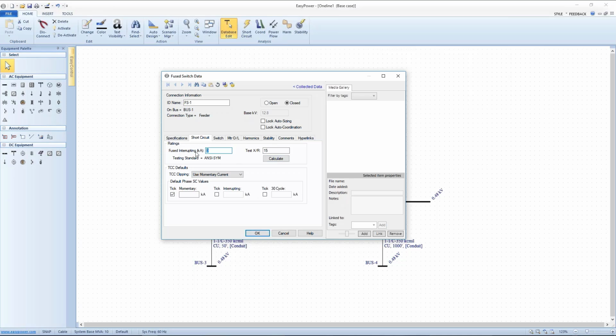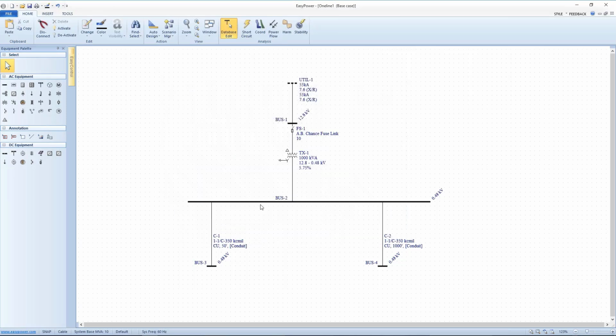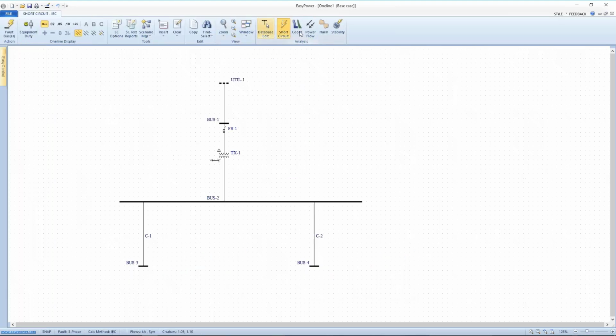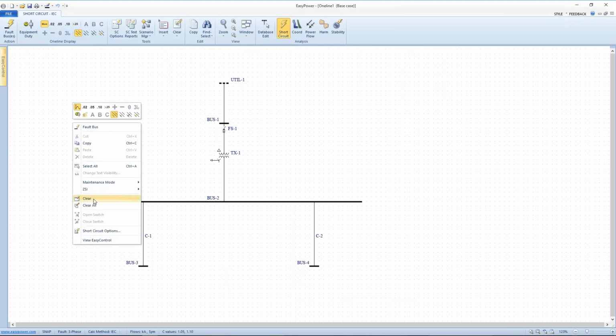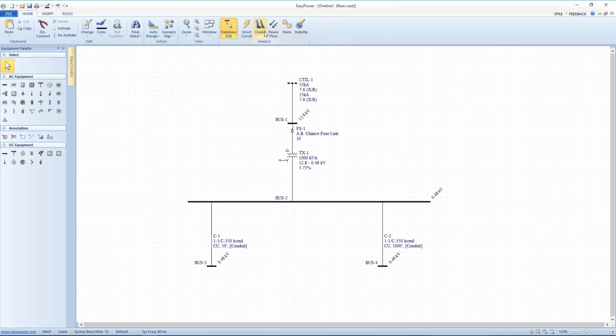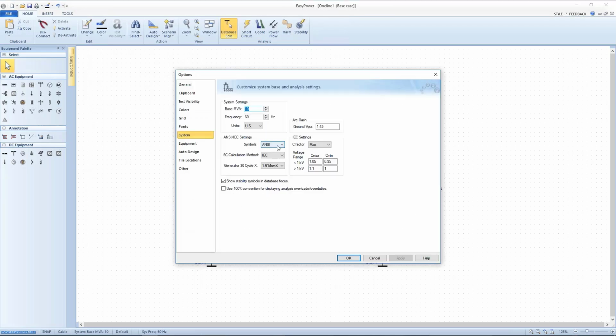Now, the interrupting rating in this case is actually that of the switch, and so the manufacturer rated this at 60,000 amps, and so we're just going to put that in for that value. He said, okay, Jim, now that we've got my one-line diagram, you can change the short circuit focus, which is this lightning bolt at the top of the screen. He says, and I want to go back, and EasyPower has the ability to do both IEC and ANSI calculations.